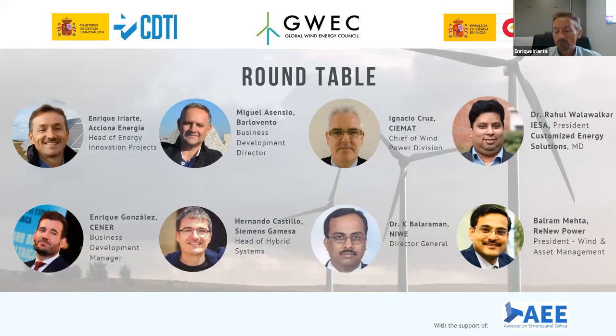For example, the pilot plant in Barasoain has two different kinds of batteries: a fast response battery of 1 megawatt but only for 20 minutes, and a slow response battery with greater autonomy of 1 hour. These are Samsung lithium-ion batteries, connected to a 3 megawatt Nordex wind turbine. We capture all the energy generated by the wind turbine, and we can manage and use all the functionalities I mentioned, deciding with the control system when and how to use them. This is also integrated into our remote control center.